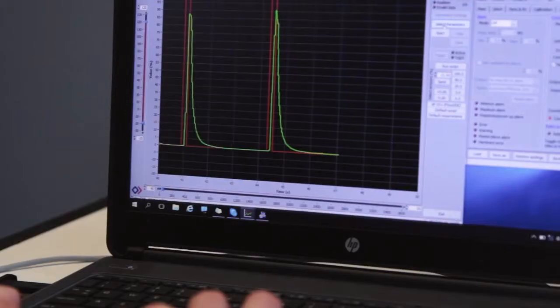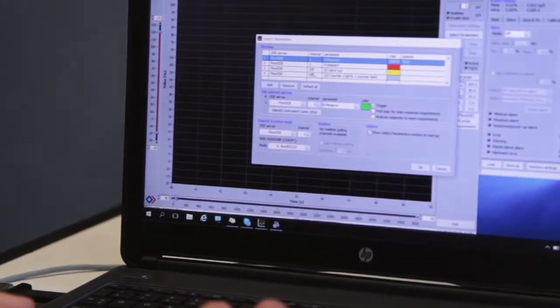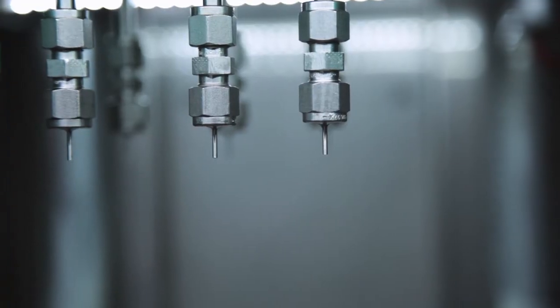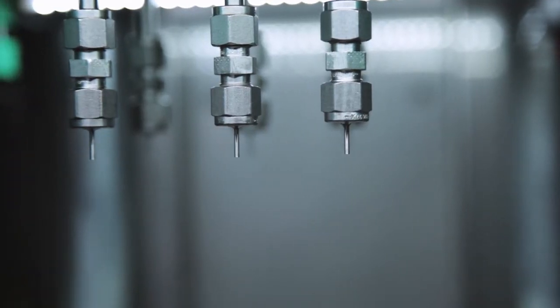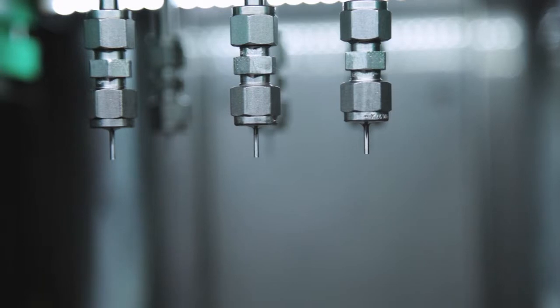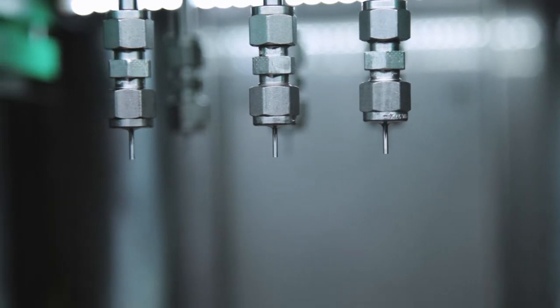By adjusting the digital parameters of the flow meter, the user can adjust the settings from ultra-fast batch dosing up to smooth proportional control.